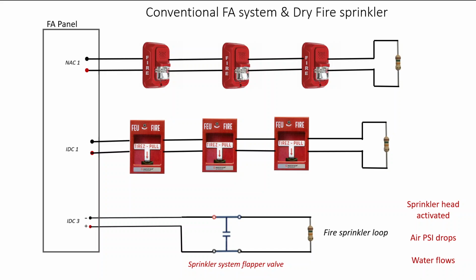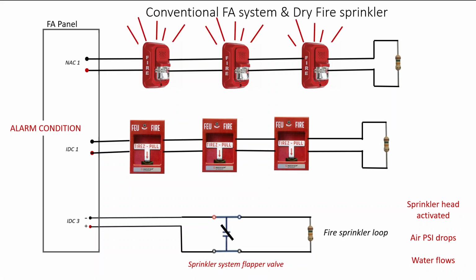Sprinkler head is activated, the air pressure drops, the water starts flowing, and we would expect for the contact to then actuate when the valve fully opens. That would cause an increase in current through our IDC loop, which this fire alarm panel will recognize as an alarm, and it will notify or make all of the NAC devices energize by a flipping of polarity.